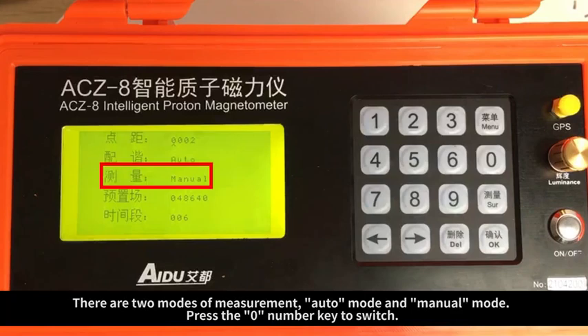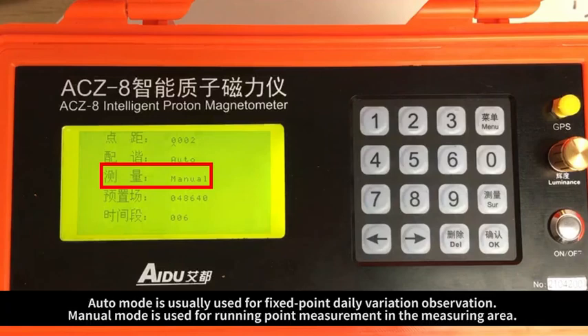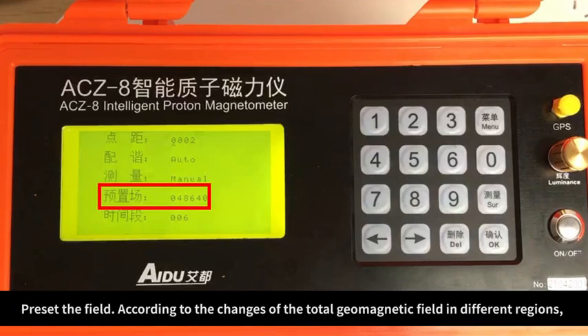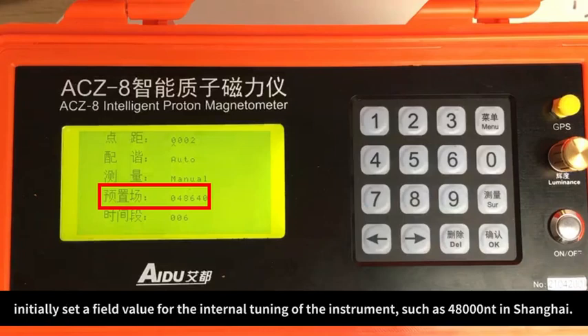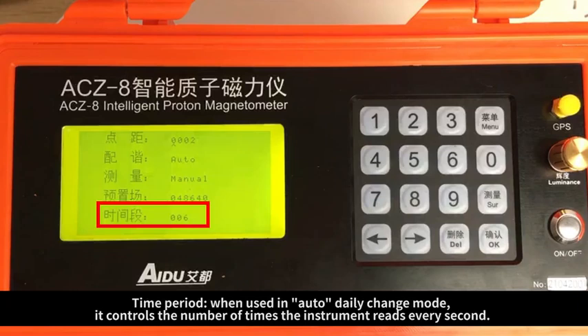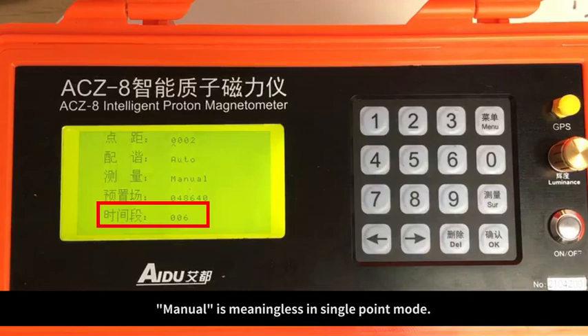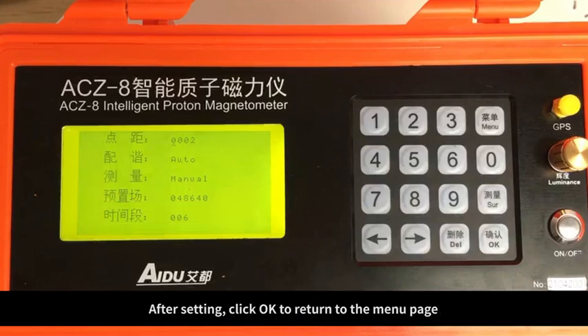There are two modes of measurement, auto mode and manual mode. Press the zero number key to switch. Auto mode is usually used for fixed point daily variation observation. Manual mode is used for running point measurement in the measuring area. Preset the field according to the changes of the total geomagnetic field in different regions. Initially set a field value for the internal tuning of the instrument, such as 48,000 nT in Shanghai. Time period. When used in auto daily change mode, it controls the number of times the instrument reads every second. Manual is meaningless in single point mode. After setting, click OK to return to the menu page.